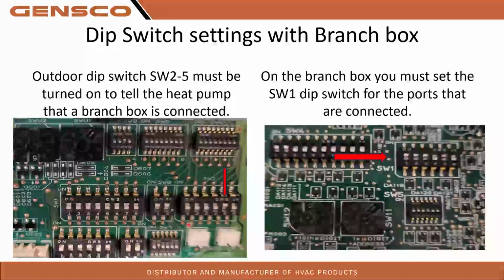Actually, this is a really good screenshot for you guys, for anyone doing the one-to-one application. Because right here on your heat pump, there's your address dials already set up with that SW25. This will be 99% of your installs right here. So if you're doing a branch box, this is exactly how your switch and address dials, and your heat pump, should be set up.